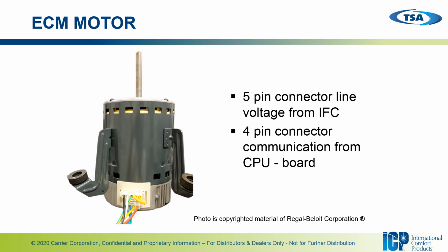Okay, you've got a 5-pin high line voltage or high voltage connector from the indoor fan control, and then you've also got a 4-pin communication or control voltage connector from the control board to the motor as well.